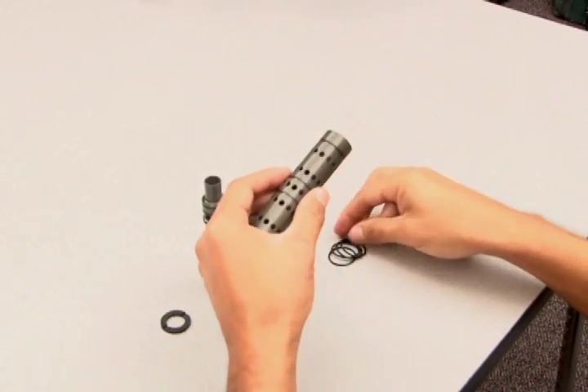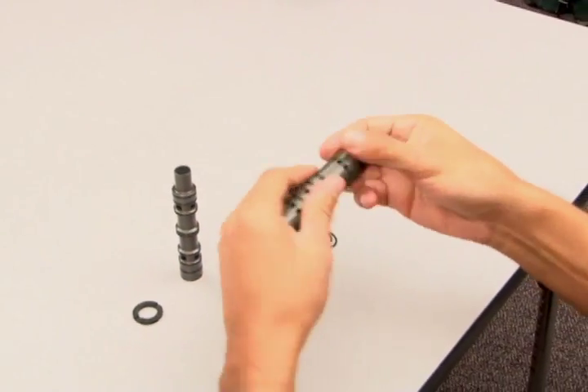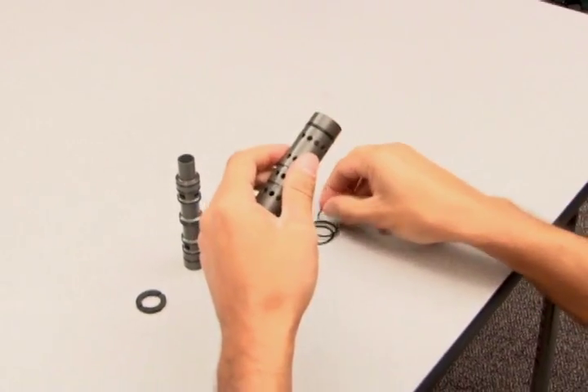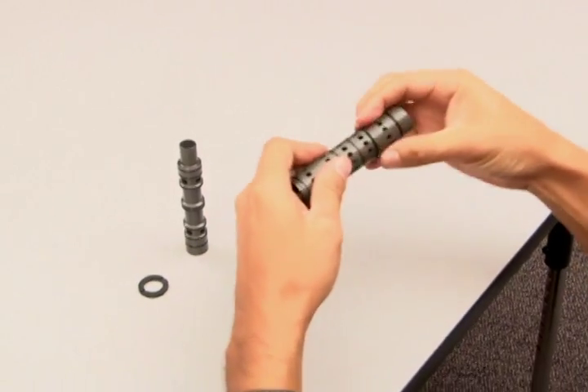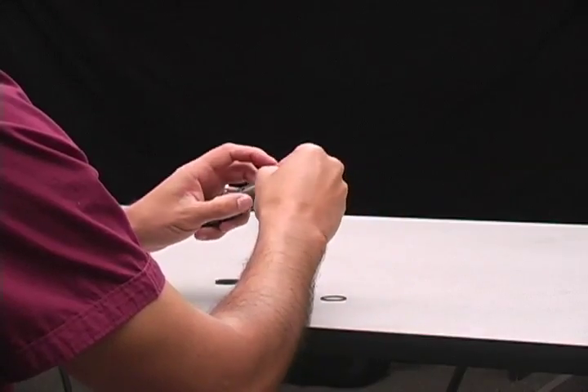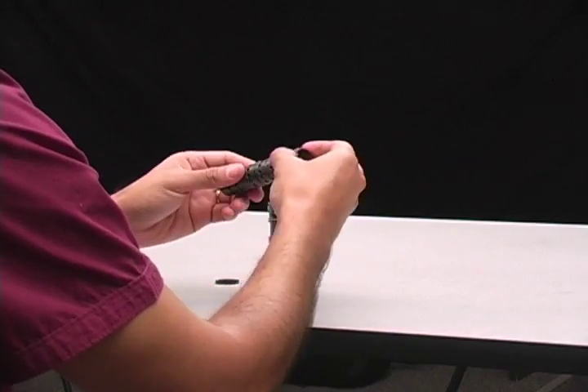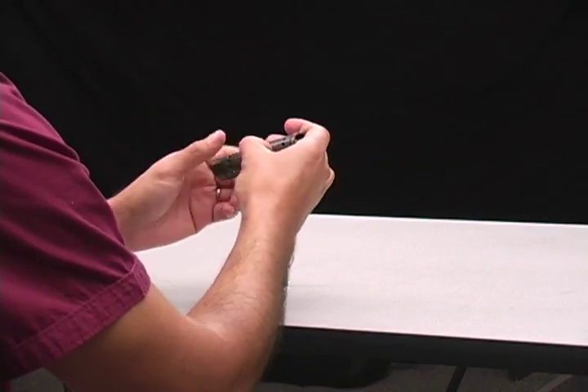To replace the sleeve O-rings, install the four new O-rings by sliding them over one end and working them down so they sit properly in the four grooves on the sleeve. The O-rings should not be twisted or rolled when seated properly. All four O-rings are the same size and can be replaced in any order. The new O-rings and sleeves should be re-lubricated before reinstalling into the pump.